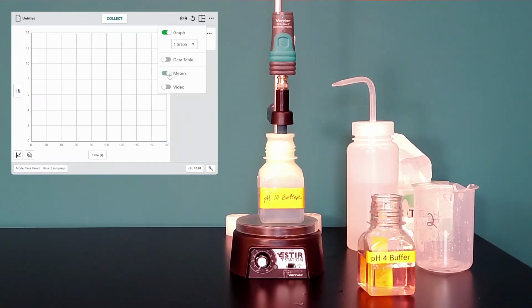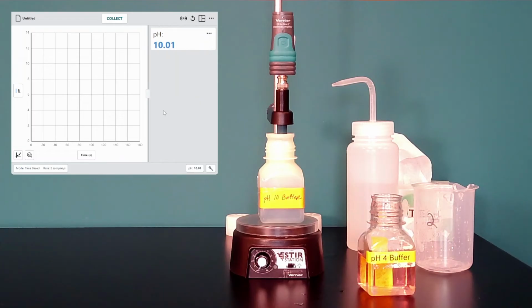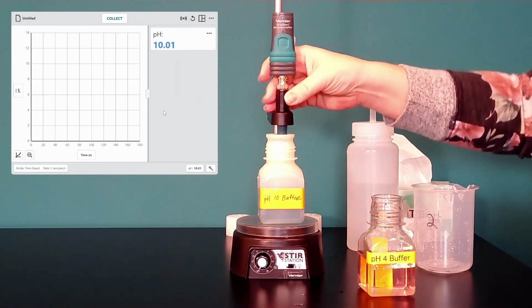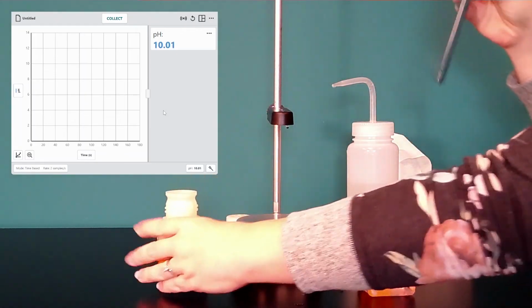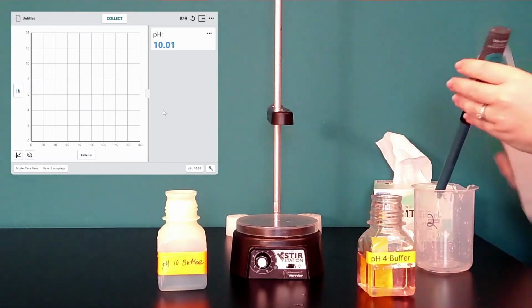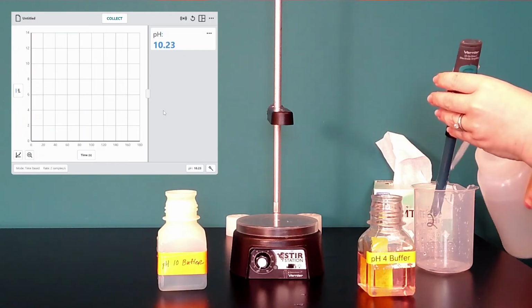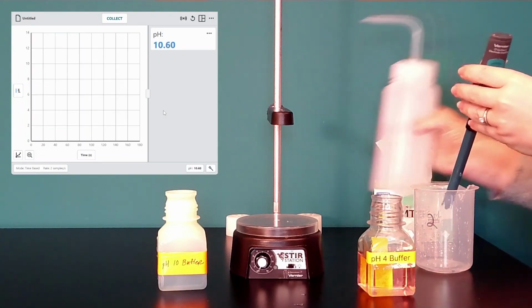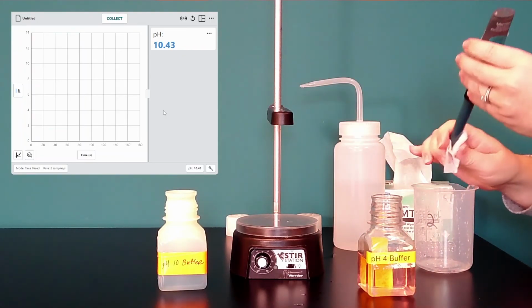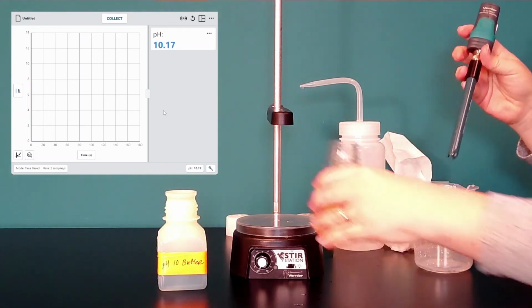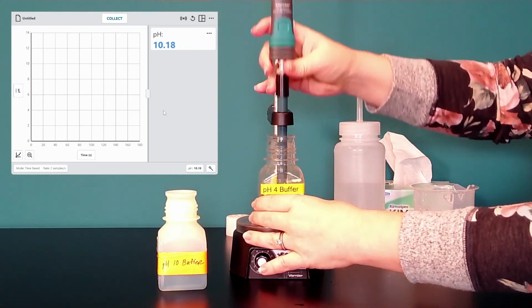For ease of view, I'm going to turn on the meters. There, that's much easier to read. It is definitely within the error. So now I'm going to put it back in my pH 4 buffer and make sure it reads pH 4 there. So I'm going to rinse with deionized water and pat it dry with the chem wipe.